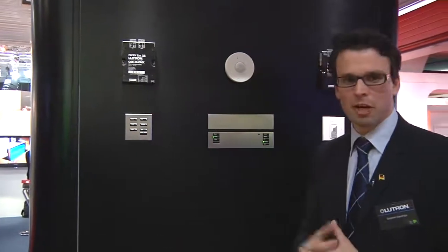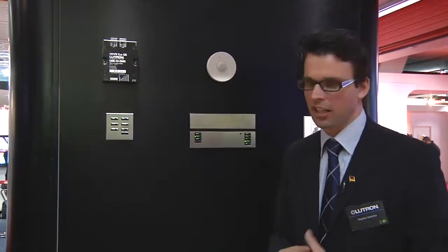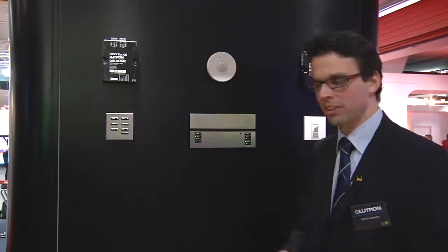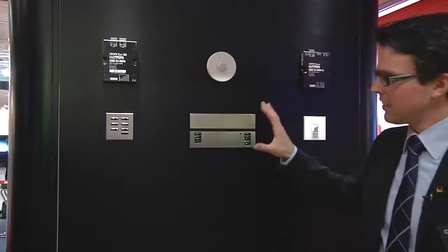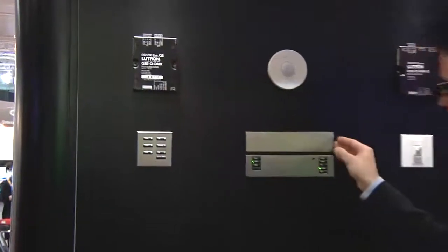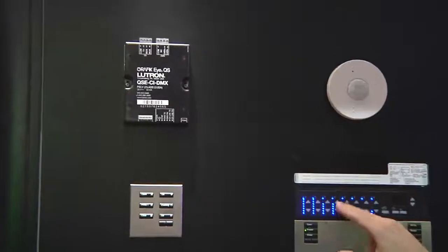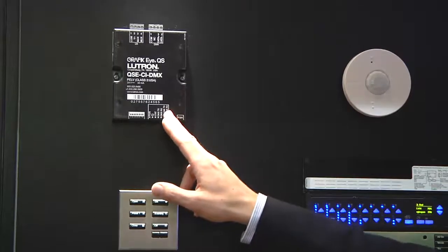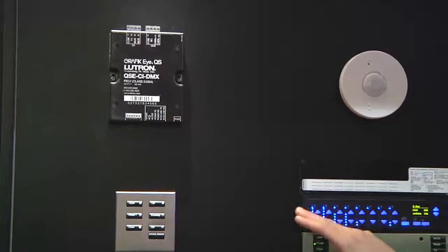For those of you who are familiar with lighting, over the last years, the number one growing light source is LEDs. And I'm sure some of your customers have asked to integrate LEDs to make colorful light in a room, in an environment. Now we can integrate LEDs in multiple different ways, and one of them is to use a DMX interface. So what we can do in this scenario is we can map zones on our Graphic Eye with a DMX channel. So for example, on this Graphic Eye here, I have 3 zones, red, green, and blue.